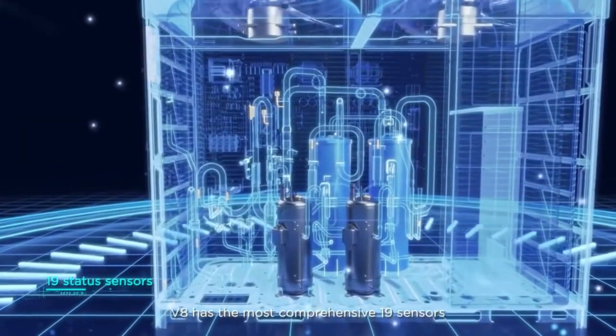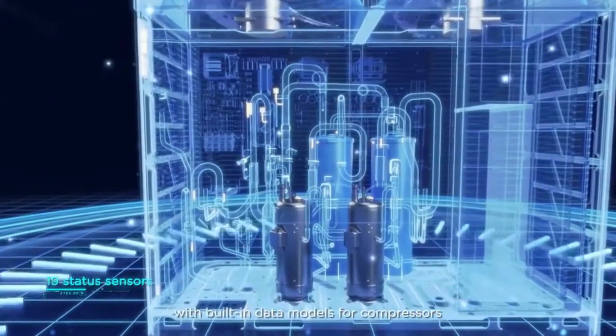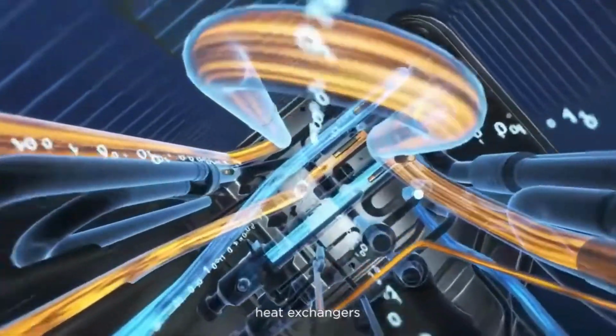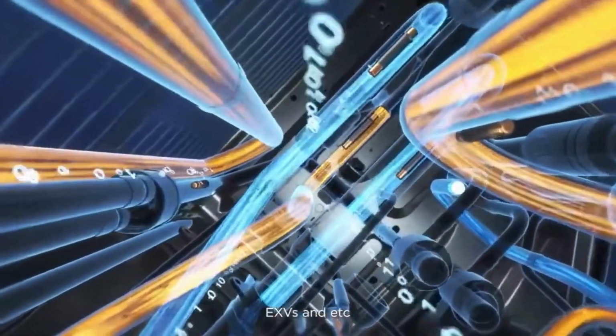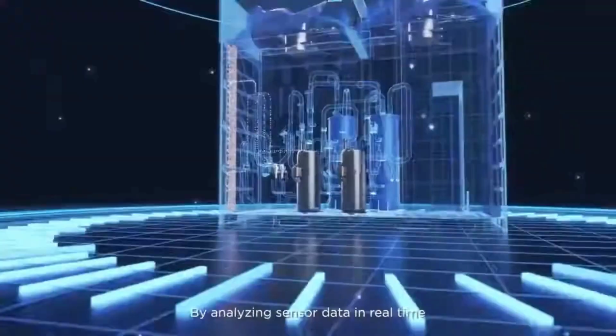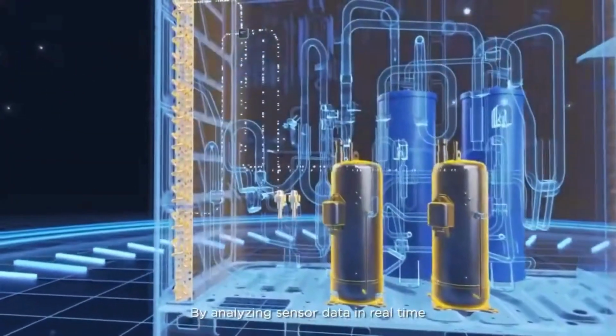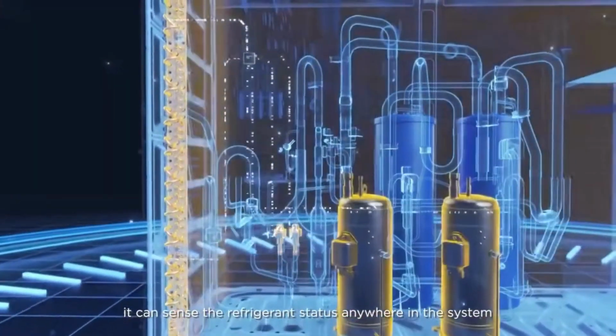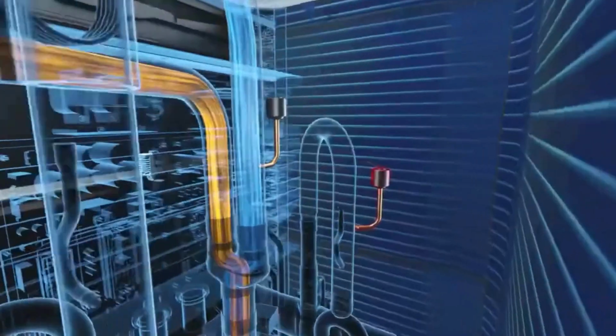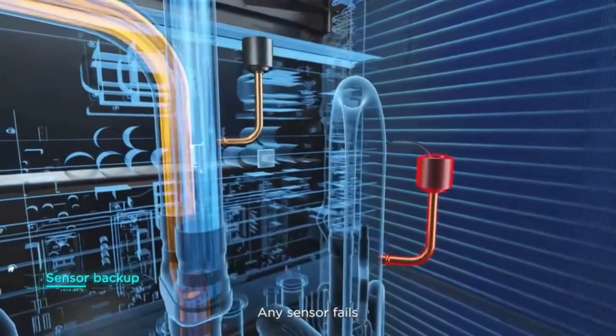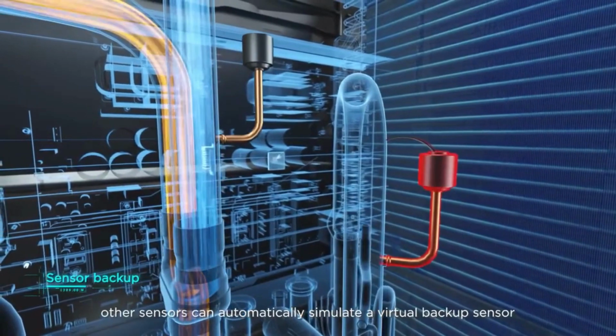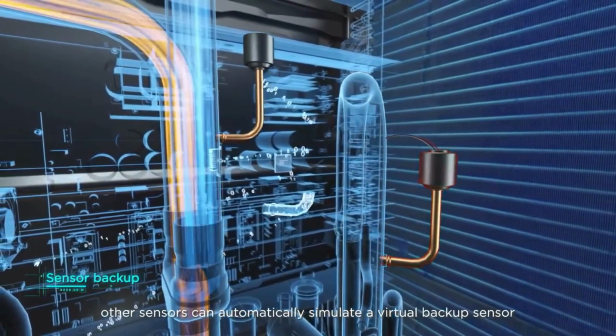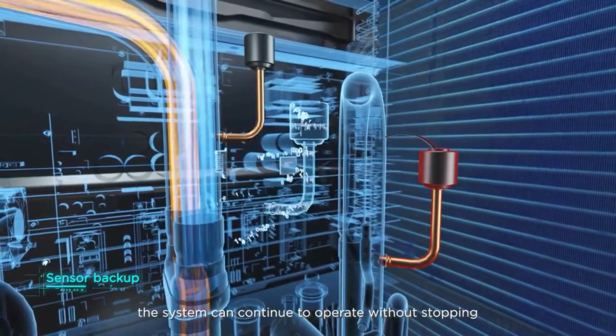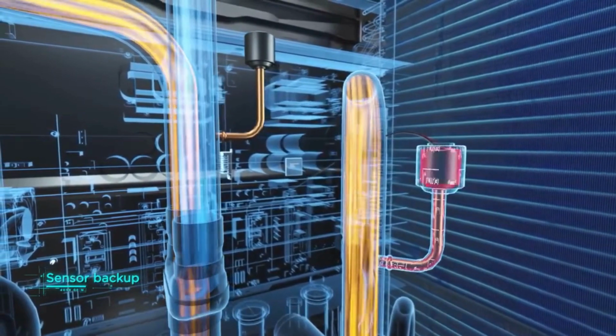Comprehensive 19 sensors with built-in data models for compressors, heat exchangers, EXVs, and etc. By analyzing sensor data in real time, it can sense the refrigerant status anywhere in the system. If any sensor fails, other sensors can automatically simulate a virtual backup sensor. The system can continue to operate without stopping.